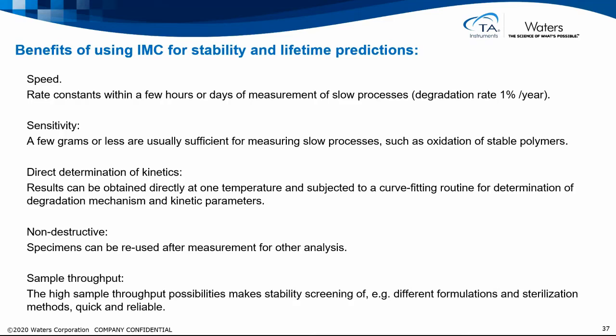So the benefits of using microcalorimetry for stability and lifetime prediction are speed. You can get rate constants within a few hours or maybe days for slow processes. Sensitivity, it's not very much sample that is needed. We get a direct determination of kinetics. It's non-destructive. Samples can be further analyzed afterwards. And the sample throughput. 48 simultaneous measurements is possible, so screening of different formulation and sterilization methods can be done quickly and reliably.